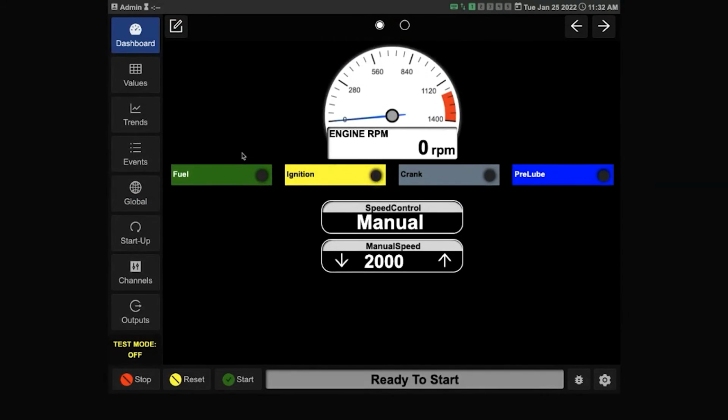And so anyway, in some ways it's similar to what can be done with Modbus, but it's a little bit backward, in that the DE4000 is actually just pushing out its information at a fixed frequency over this MQTT channel, and then whoever happens to be subscribed to that can receive that data and then choose what to do with the information.